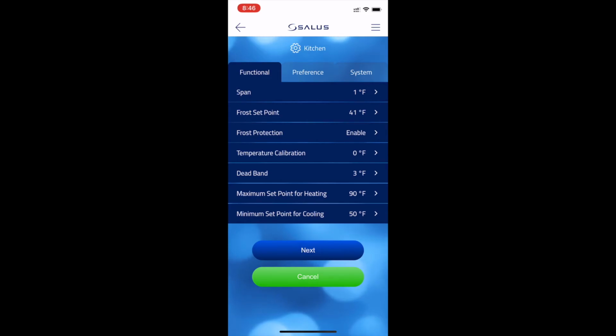The functional parameters are pretty self-explanatory in terms of enabling and disabling frost protection and setting a frost set point, as well as setting a maximum heating set point and a minimum cooling set point. The parameters that may be of particular interest are span, which sets the difference in temperature between when the heating or cooling turns on or off, also referred to as hysteresis. The deadband, which sets the separation between heating and cooling in number of degrees. And then the temperature calibration that allows you to offset the display of the thermostat.